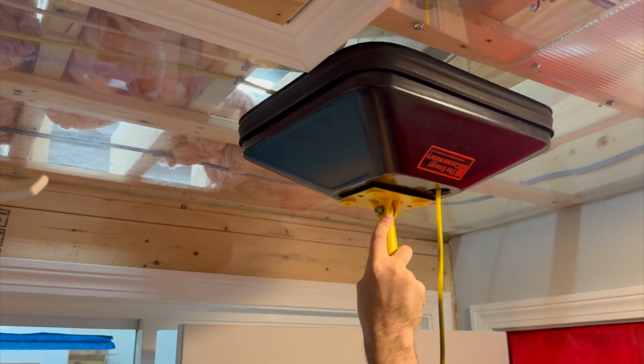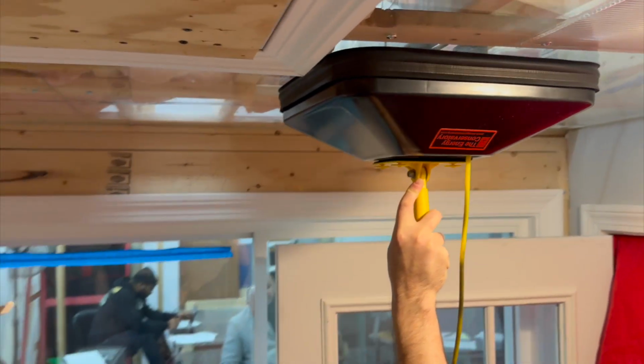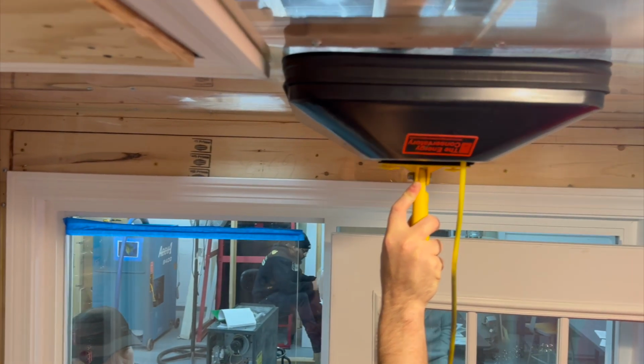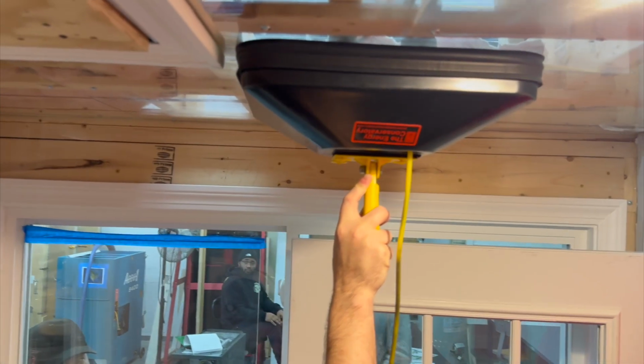All right, I'll take this close. Oh, there we go. All right, it has a reading of, jumping a little bit, but minus 22 pascals. Right, we want it as close to 0 as possible, which means air sealant is needed in this area.